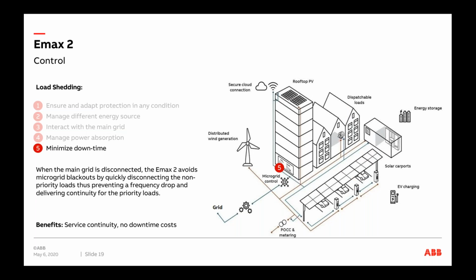And then there's the downtime. So we want to avoid any kind of blackouts. We want to avoid downtime for our end customers. When we have a limitation to power supply, this comes into play, the way we look at load shedding. So you can have a certain scenario set up within the logics of Emax 2 trip unit where you have priority and non-priority loads based on reduction of energy or power supply or restrictions on power supply. We can switch on to just the critical loads or priority loads, as we call it, and then have the non-priority, non-essential loads switched off. That can be worked out through a logic within the Emax 2 system or the trip unit.